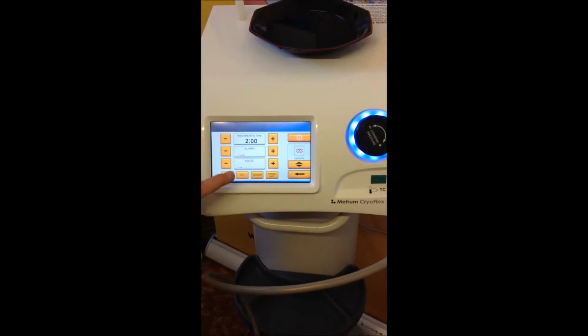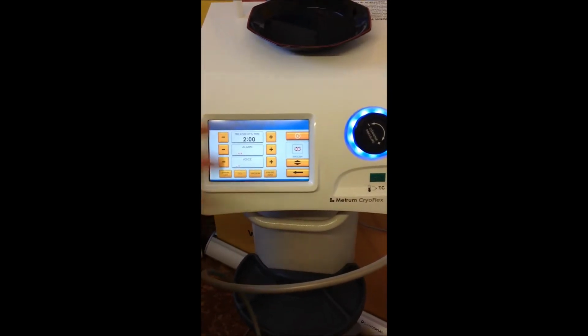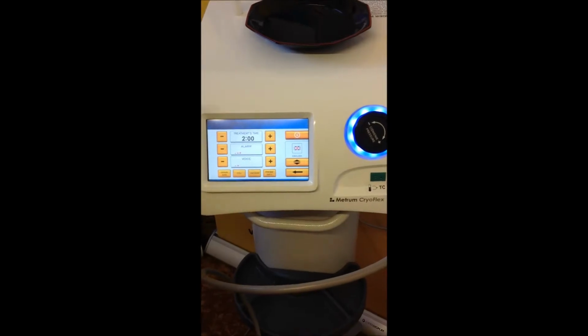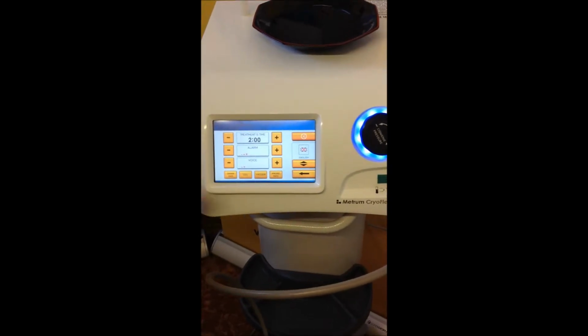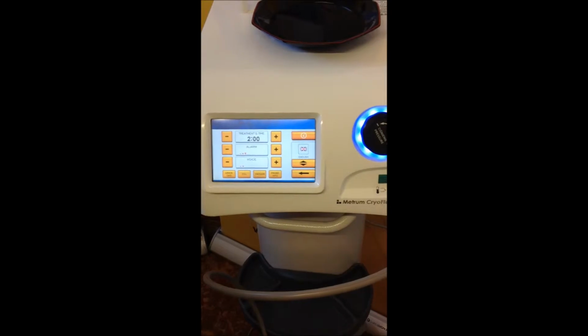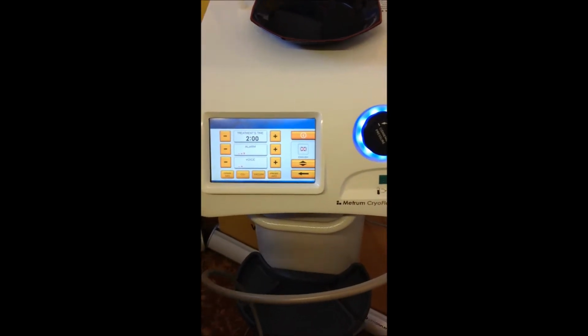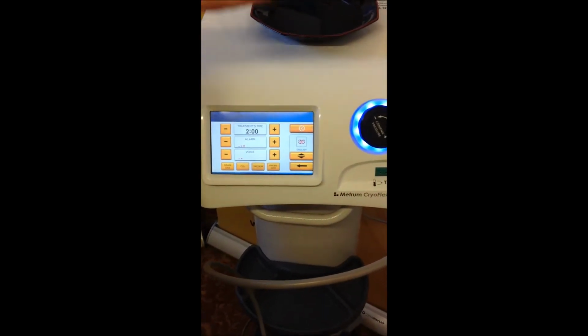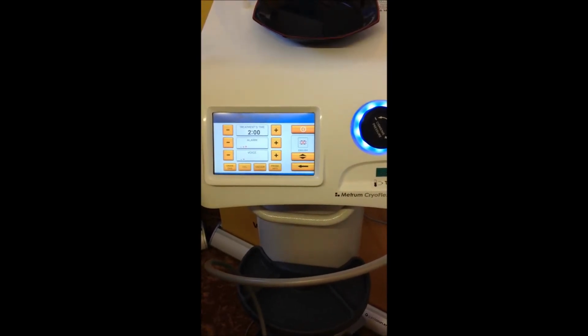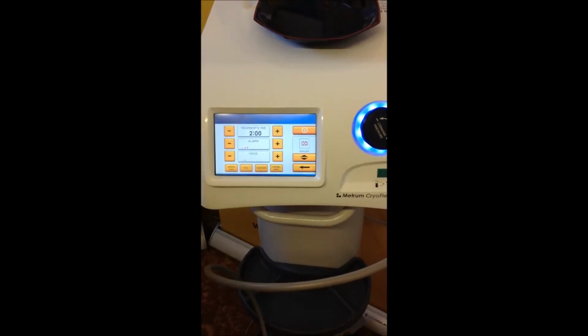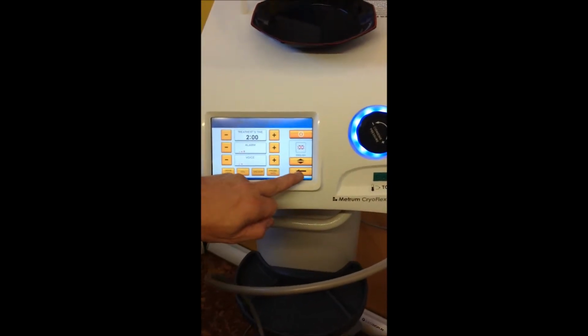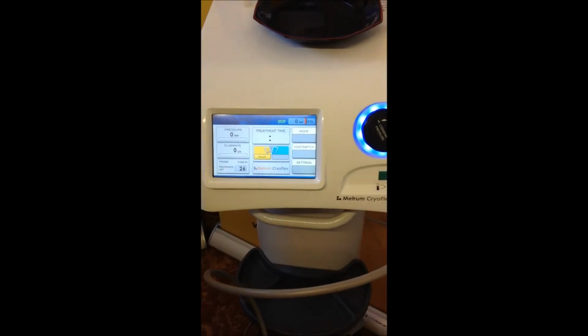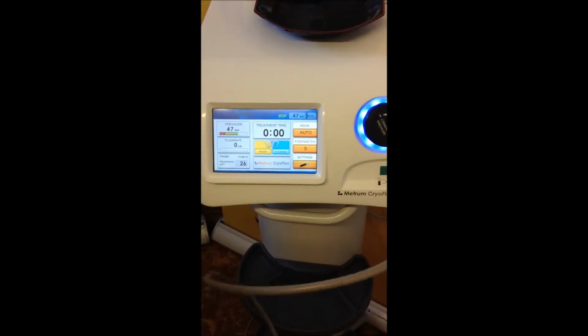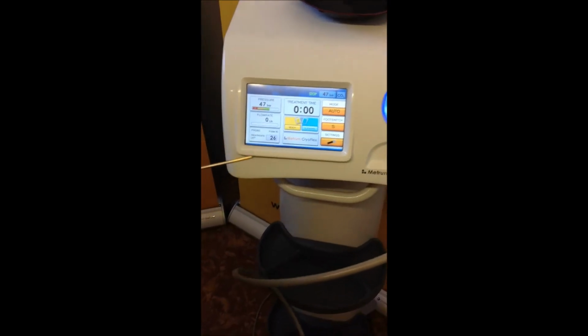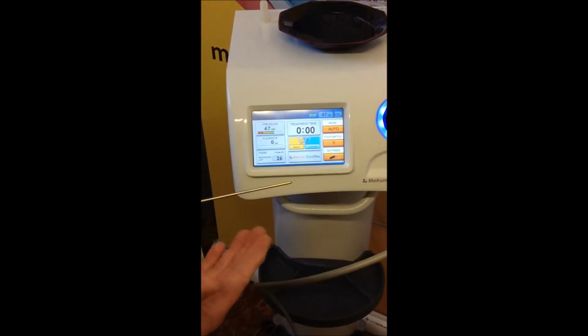We have CO2 because we're going to work with CO2. Of course, if you work with N2O, this can be changed. An important button here is the drain gas button. Why is this important? When you stop the procedure, the cooling generator should be drained of all the gas. Otherwise, your machine stays under gas pressurization, and this is not what we want. To return to the screen, we just press the arrow. Standby mode.